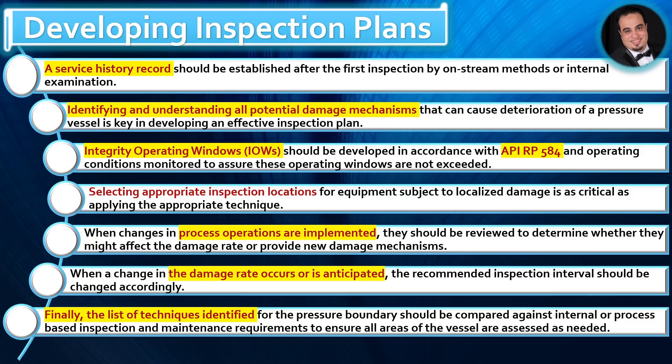Integrity operating windows (IOWs) should be developed in accordance with API RP 584, and operating conditions monitored to assure these operating windows are not exceeded. When changes in process operations are implemented, they should be reviewed to determine whether they might affect the damage rate or provide new damage mechanisms. When a change in the damage rate occurs or is anticipated, the recommended inspection interval should be changed accordingly.